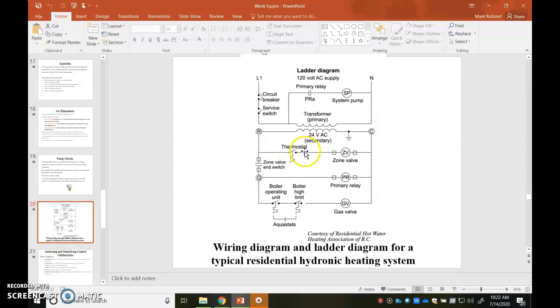So you'll have a thermostat that closes, and that thermostat will power what's called a zone valve. And that zone valve is a 24-volt valve. It's a load, and what it does, it opens and allows the water to start flowing, or if it could flow. When it fully opens, it closes a switch called the end valve, zone valve end switch. And at that point, the R continues through, and then it will power this primary relay. That's a coil. That will then close the system pump right there, PRA, and the system pump closes.